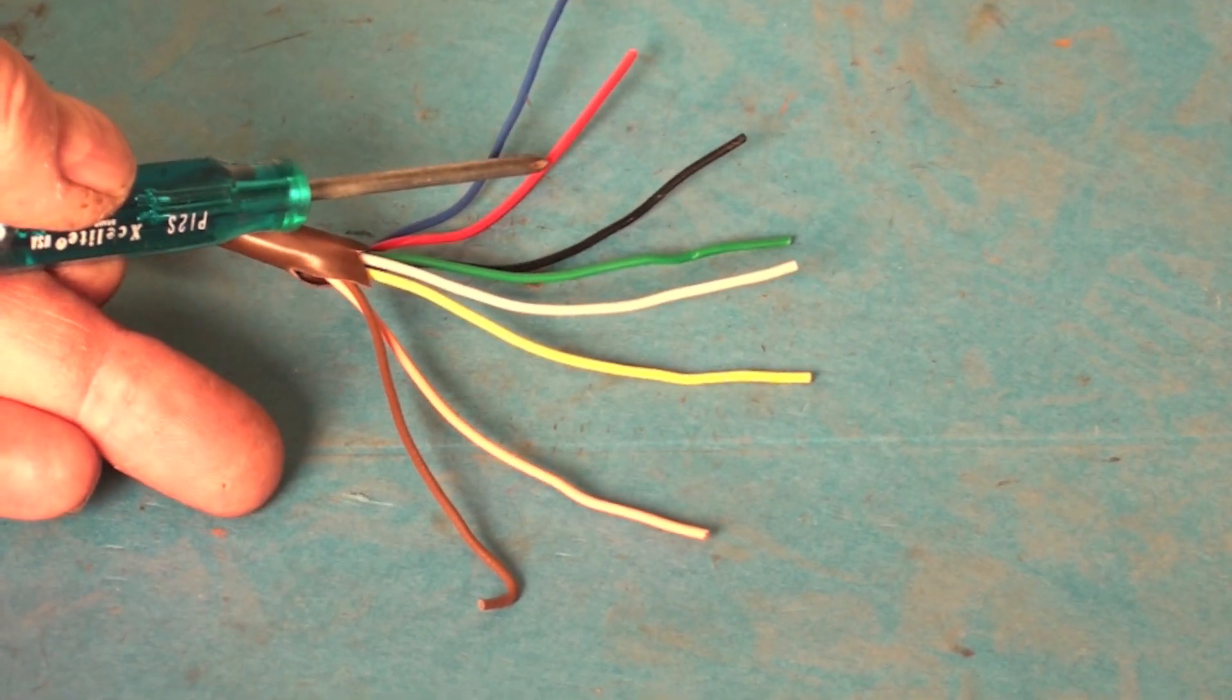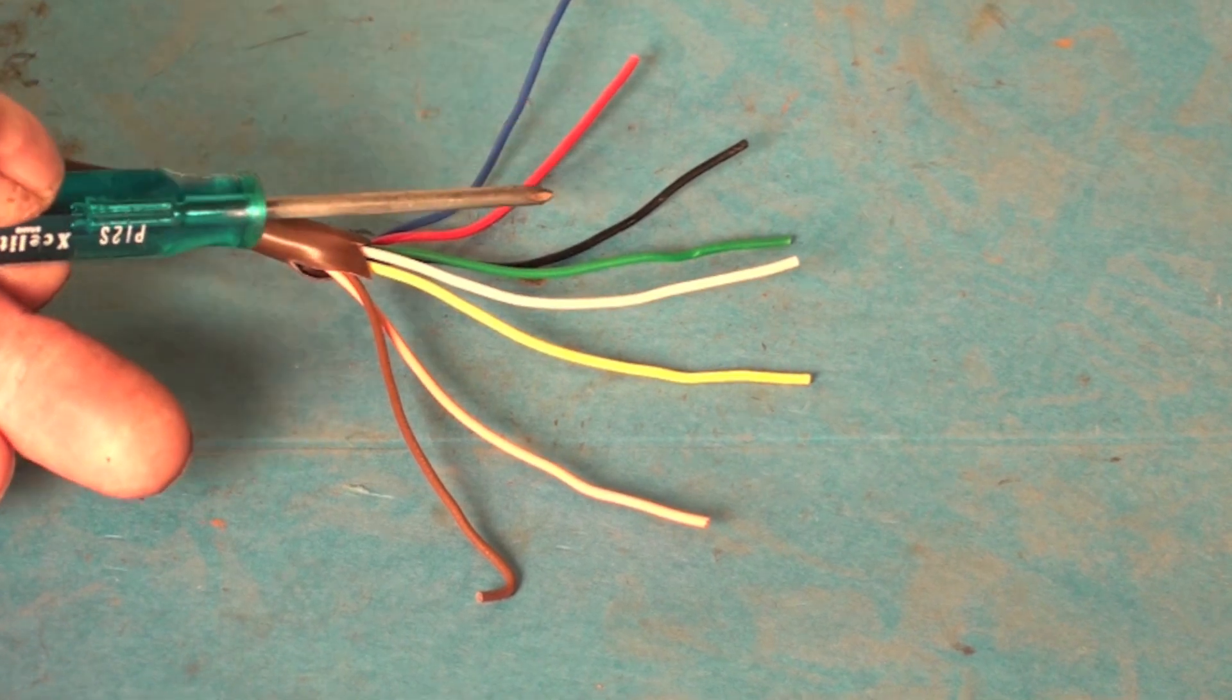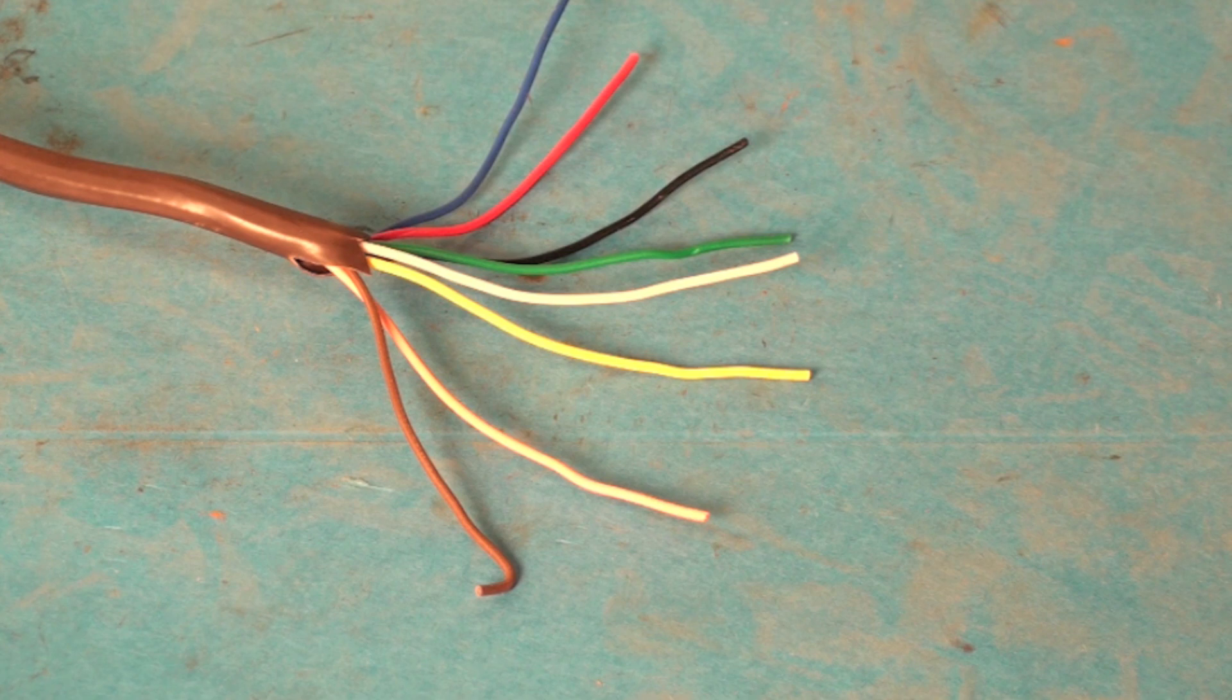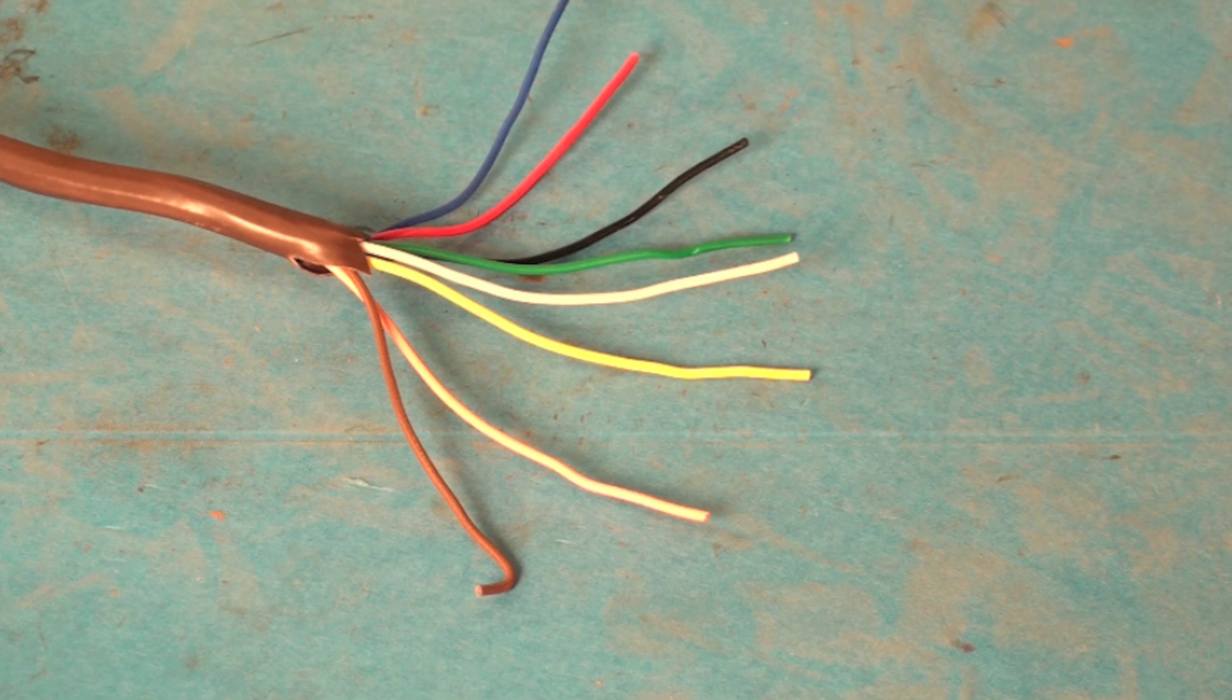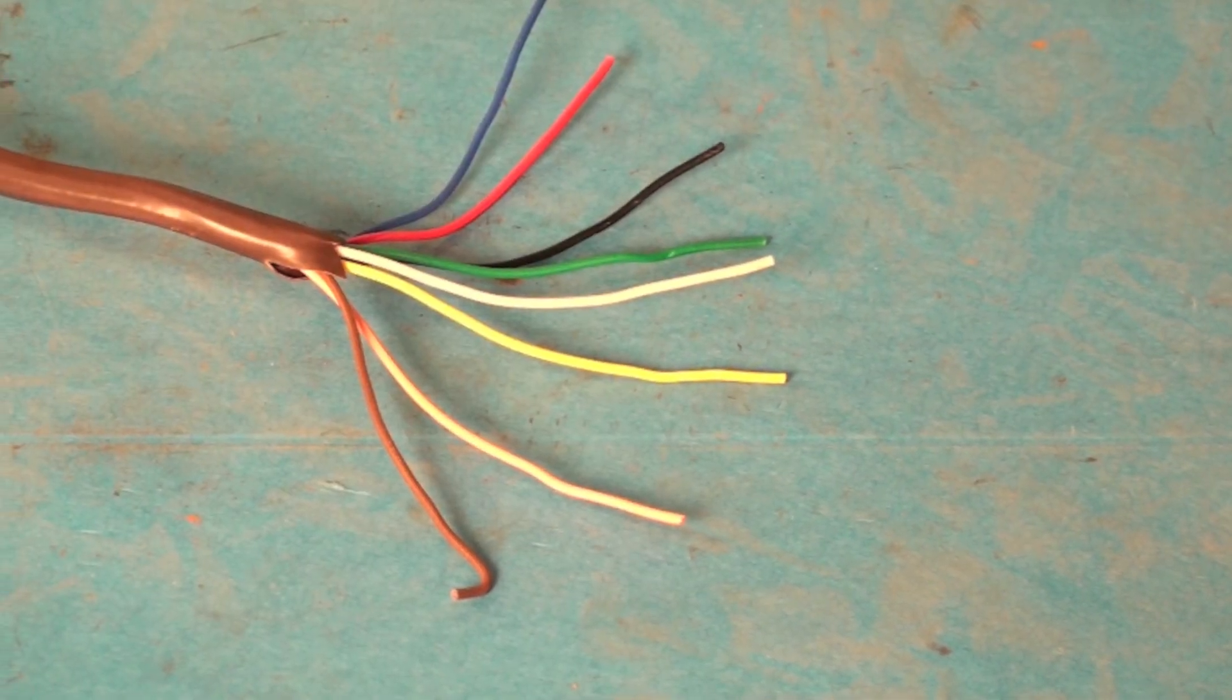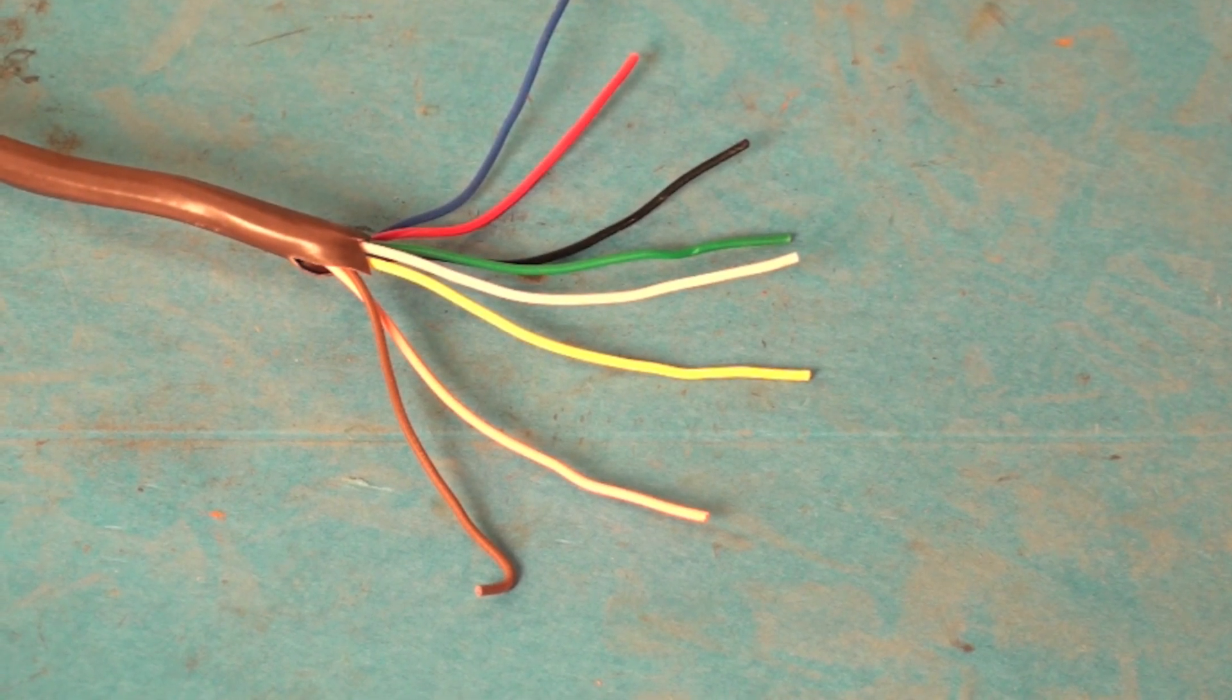Red is power. Blue is reversing valve energized in heat. Orange is reversing valve energized in cool. Black is common. Green is fan and white is heat. Yellow is cool. That's as close as I can get on this.